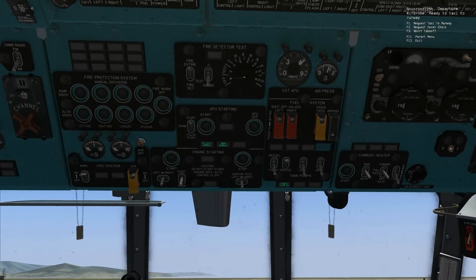We're going to set our start selector switch to the left or right engine, depending on the wind. There is no wind today, so we're going to set that there. We have a caution: if the power turbine intake temperature rises above limits during start, initiate the shutdown using the stop cock. Do not press the stop button.